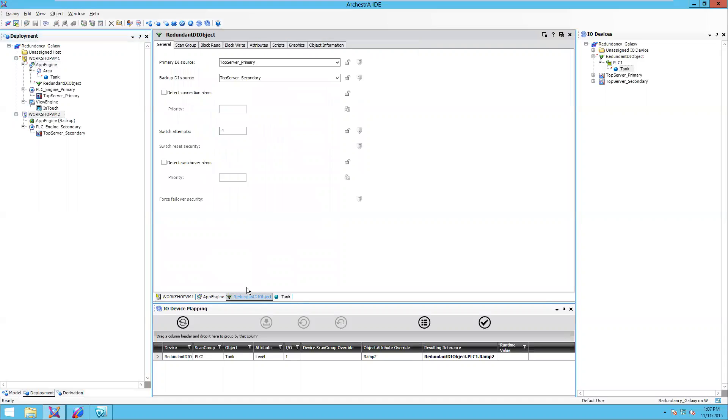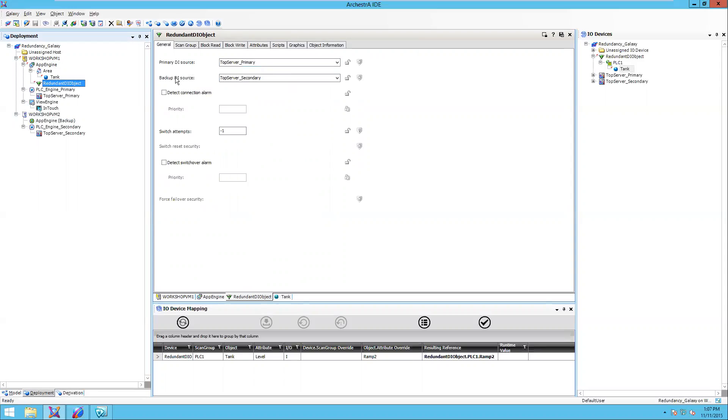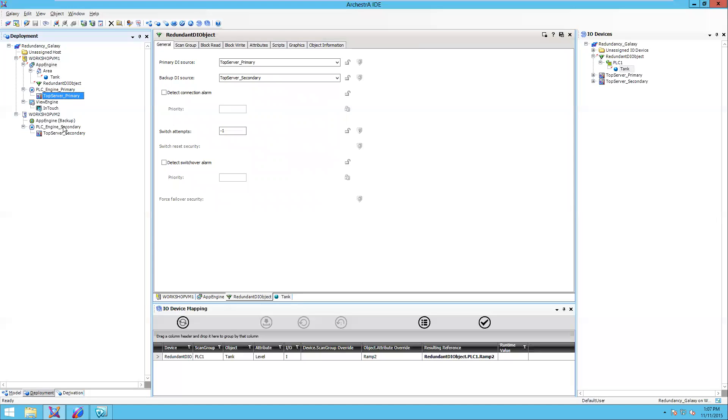Next, I've got a redundant DI object configured. A redundant DI object is what provides the failover between the primary and the secondary IO server. I've identified my primary and backup IO server. In this case, I've got a top server primary and a top server secondary. Notice that top server primary is running on an engine as well as my top server secondary is running on an engine on Workshop VM2.